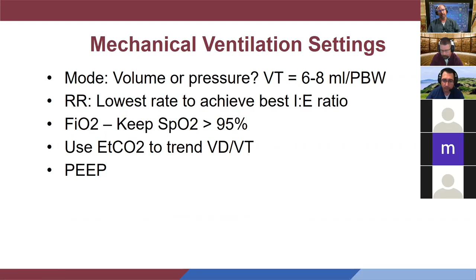All these other ventilators have some type of dual control, but the advantage of a volume mode is you get to set a rate and a tidal volume, which guarantees minute ventilation. The advantage of dual control versus volume control, though, is you actually have an algorithm built into the device that titrates the lowest possible pressure to achieve the tidal volume based off compliance and airway resistance. So if you think of an asthmatic or COPD patient who has increased airway resistance, you're like, well, okay, this might be a good mode to put them on.